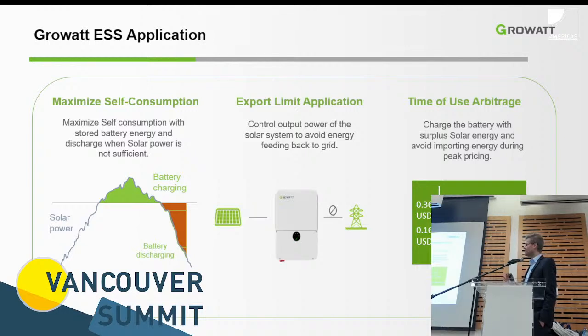The function of the battery and how you can use it is not focused or specific for Growatt, but there are certain operation modes that you typically use a grid-tied battery system with. One of the big ones, not so much in Canada, is self-consumption. So for example, in a net billing environment where you get very little money when you feed into the grid, but the consumption cost of taking power from the grid is relatively high, there's an incentive for the customer to use as much solar power as possible that they produce themselves, versus giving it away for, let's say, 6 or 8 cents into the grid.